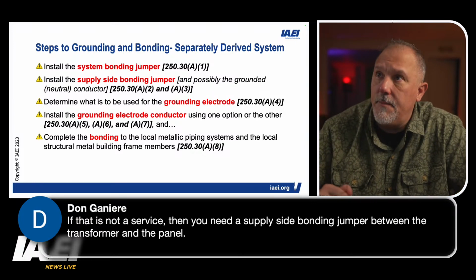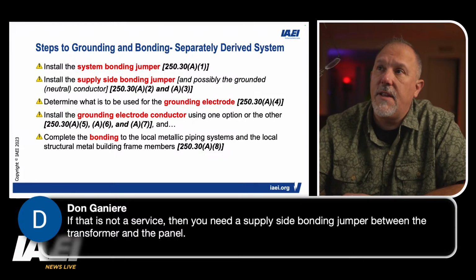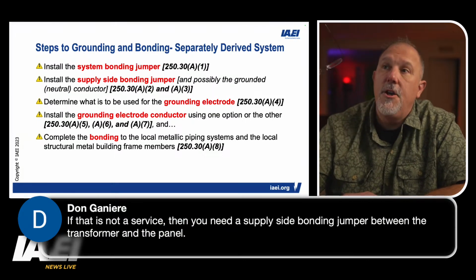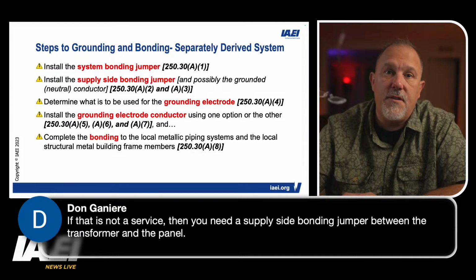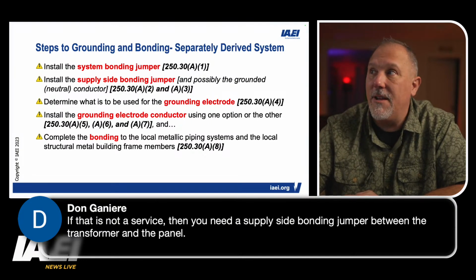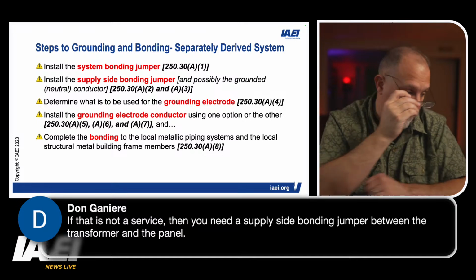Install the system bonding jumper. So you have to have a system bonding jumper. You have to have the supply side bonding jumper. You have to figure out what you're going to use for your grounding electrode. That's in 250.30(A)(4).